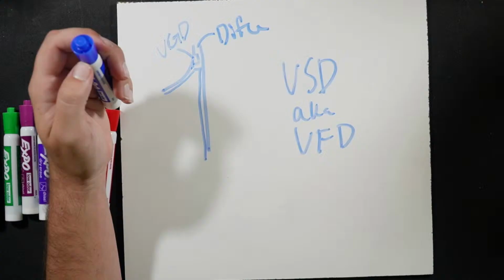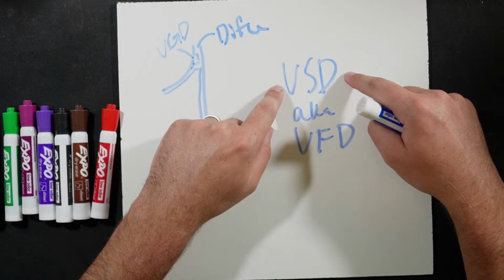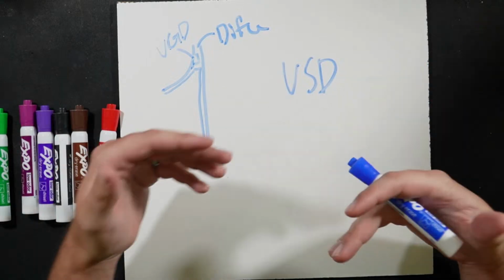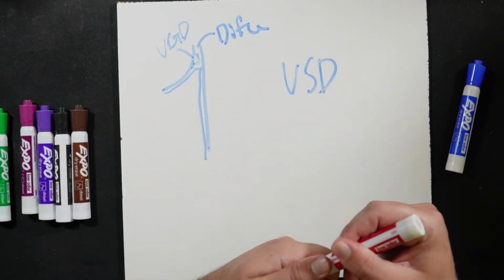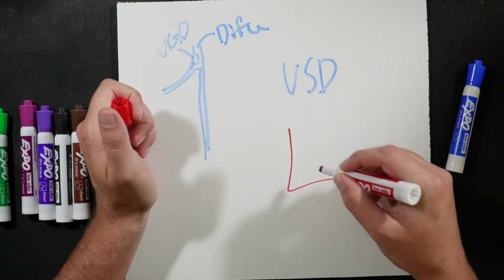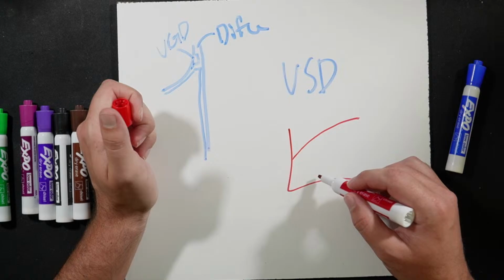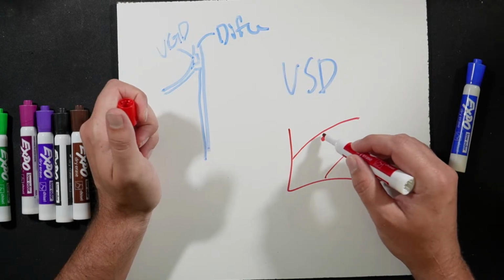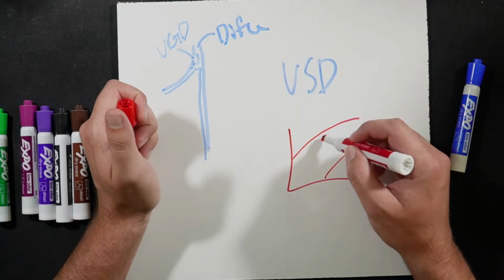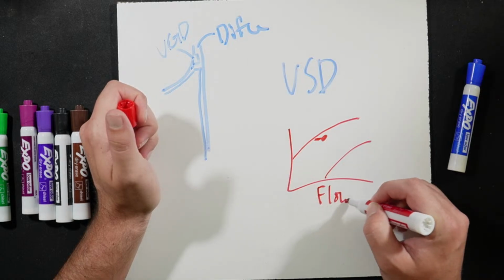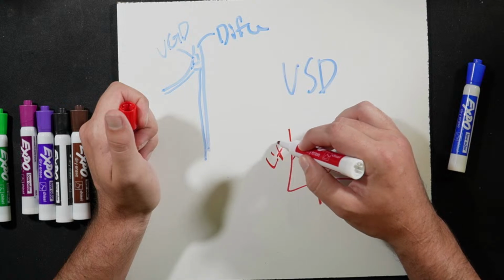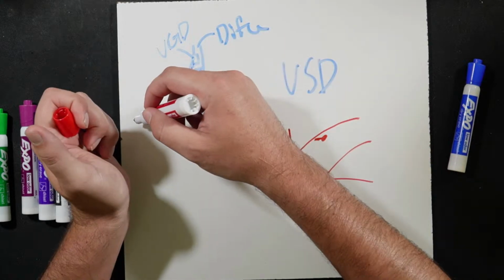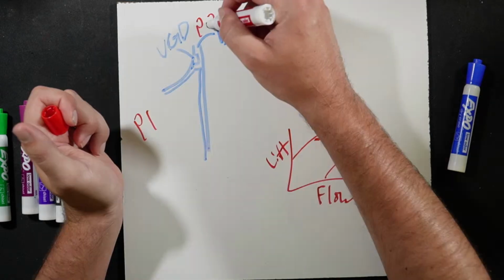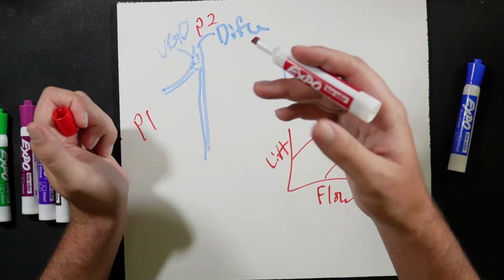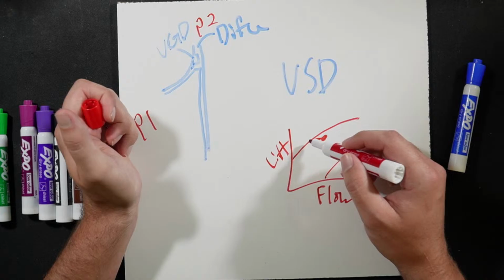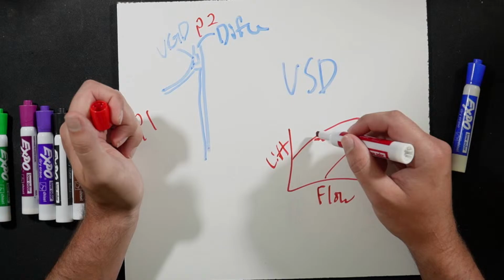Part of what we can do is, with the VSD first, we're going to slow the compressor down as much as we can. Now we still have a surge curve to worry about. On that surge curve, we have our graph, we've got our surge line, we've got our choke line, we're somewhere in here. And then as we slow down the drive, we are pushing over, because this would be our flow volume and this would be our lift value. So this is how much lift we have across this impeller. So this would be pressure 1 on lift, pressure 2. The difference here is your lift.